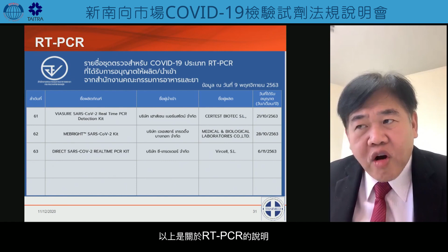This is for the RT-PCR. Now we come to the antibody for automation, or rapid test. They use the same criteria and consider three parts. One is the diagnostic sensitivity. You have to provide a sample of more than 50, N is 50 samples, and if in the evaluation you have a sensitivity of more than 85%, you will have approval for the sensitivity. The specificity should be more than 98%. Then they will look at non-specific reactions, which should be less than 10%.